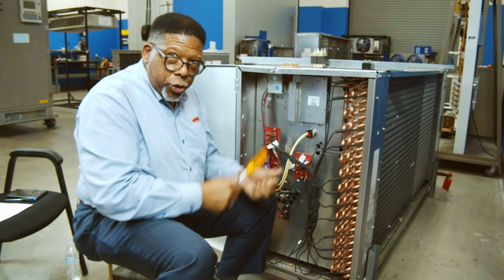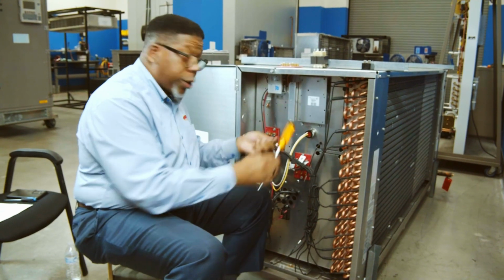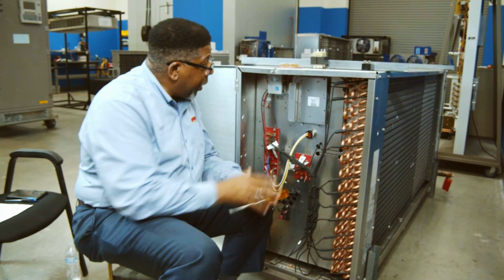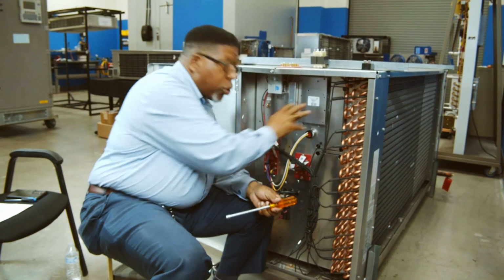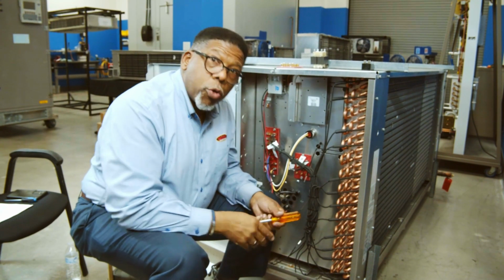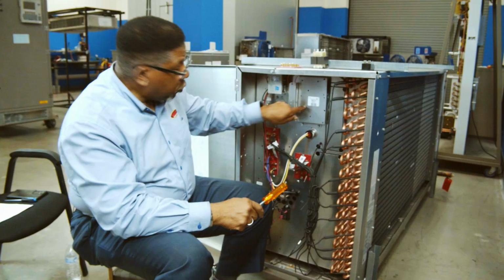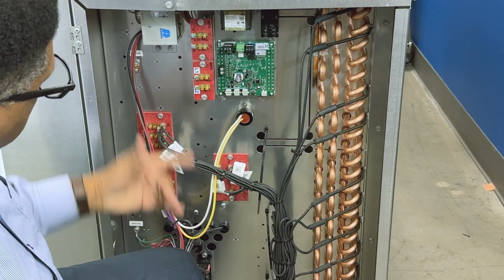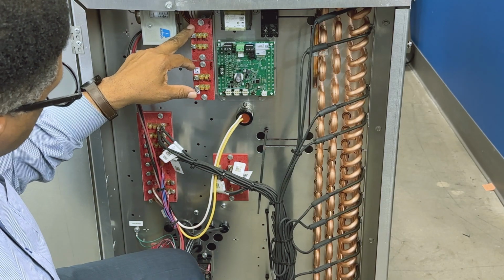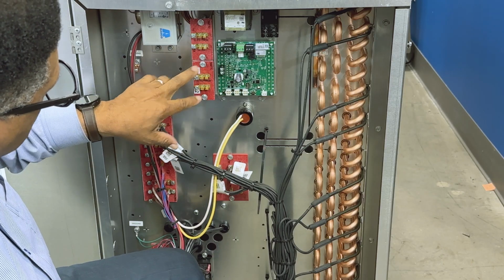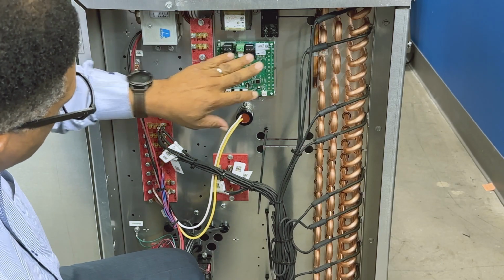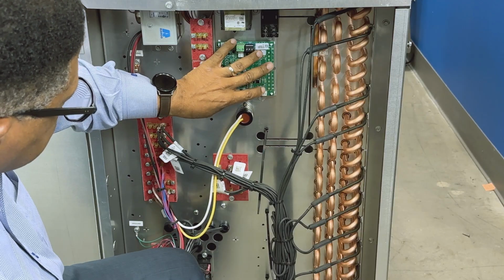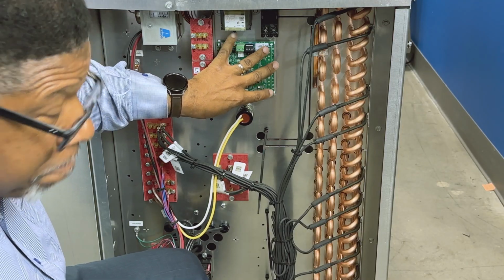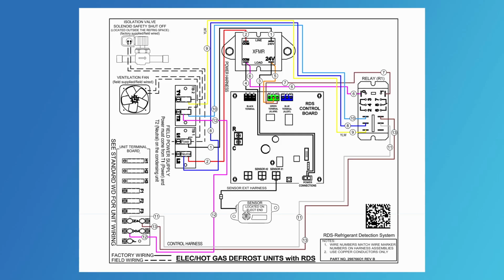Now we have a large unit cooler, an LUC, that we're going to put the RDS kit on today. It should come with the bracket pre-installed or in the kit that you get when you order it. Either way, that's what you're going to see. All right. So you have your terminal strips there, T1, T2, L1, L2, your actual step-down transformer, your relay, and the actual RDS control board itself. Remember to reference the wiring diagram located inside the access panel of the large unit cooler.